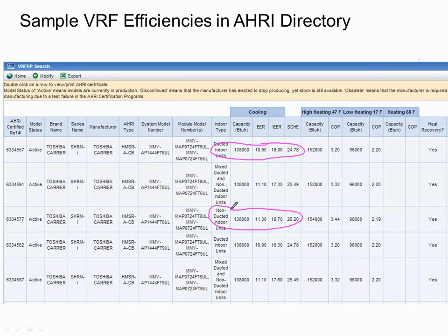So you will see all of the efficiency numbers, both full load, part load, and combined numbers, all get better. And even this is true on the heating numbers too, by the way. They're all going to get better as I go up in efficiency, as I get rid of some of my ducted units. And then the mixed ones, ducted and non-ducted in the same system, they're going to be somewhere in between ducted and non-ducted in terms of efficiency. Let me clear that off and we'll keep on moving here. So that's what the indoor type is for and why you have different ones in that bucket.